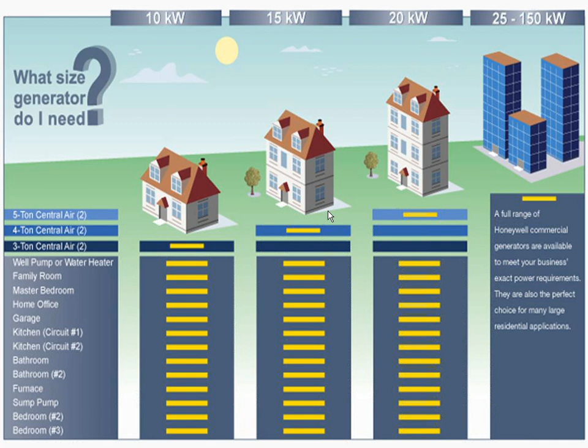What I want you to notice is that on the side where it says 5-ton air conditioner, there's a little 2 after it. That is because we can physically hook up 2 air conditioners to the circuit board inside of the transfer switch. The problem is a 20 kW is never going to start 2 5-ton air conditioners. What it will do is start one at a time. So in a 2-story house, maybe one unit is doing the first floor. You want that one on, the thermostat in the on position during the day, and then turn it off when it's time to go to bed, and then you turn the upstairs one on. So you can hook up 2, but don't think that the generator is going to start 2 5-ton air conditioners.